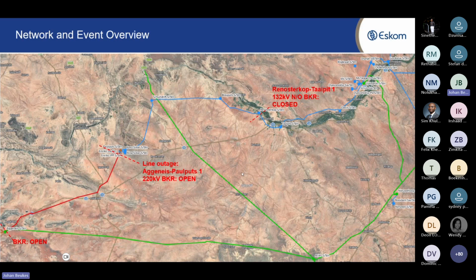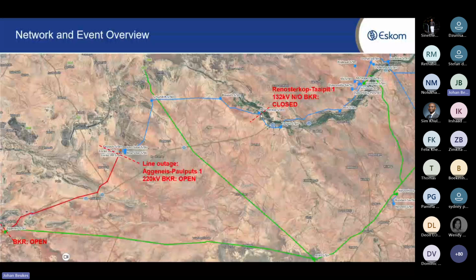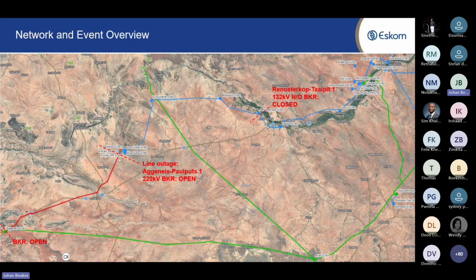And if you look at this picture, there's the main transmission substation that feeds this area from 2 sides, from Aggeneys, Aries, and then from Aries to this side to Paulputs and Renosterkop. So they took out that piece of line, and there's normally an open point at Renosterkop. To do maintenance on the Aggeneys Paulputs 220 kV line, they close that normally open point and feed the Paulputs substation from the other side, a much longer distance.